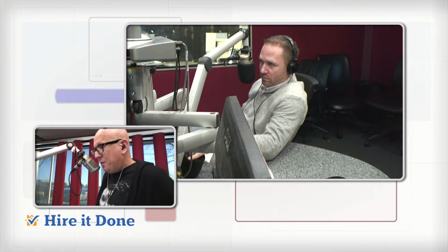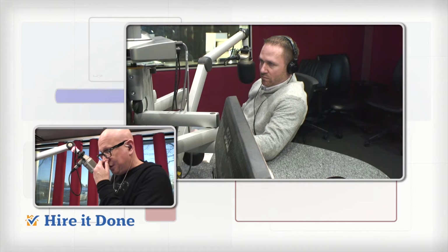Here's a text. My main floor is significantly cooler than my second floor. Some vents feel like there is little to no air coming out, the one furthest from the furnace, and I have a crawl space that's in good shape, used for storage and furnace located down there. Should I install insulation in the crawl space to help heat my main floor? Would that help? Well, if you're not feeling any distribution coming out of the ducts, you have a distribution issue. So you need to manage that.